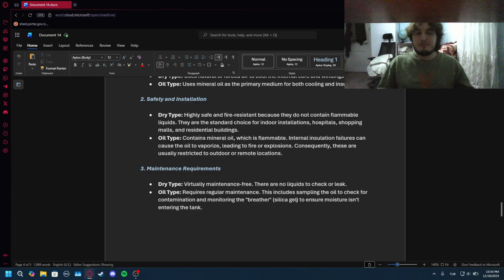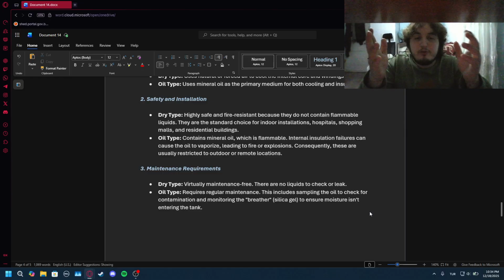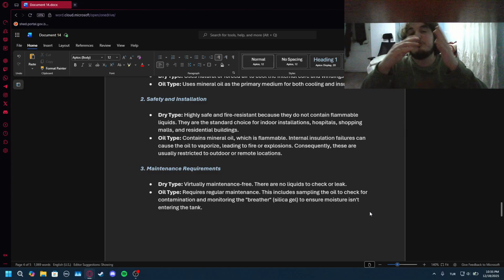Oil type requires regular maintenance. This includes sampling the oil to check for contamination, monitoring the breather silica gel to ensure moisture isn't entering the tank. You do not want water inside. You do not want air inside. You do not want air bubbles inside. Because all of these irregularities can cause explosions.